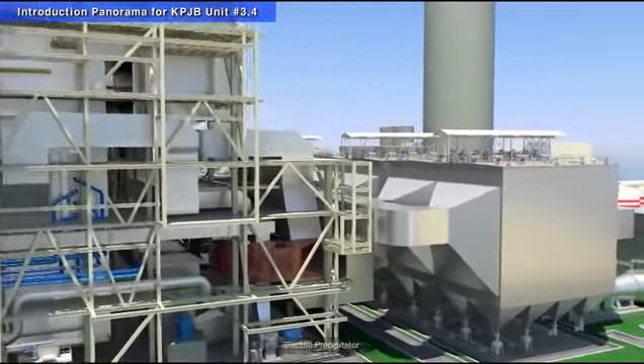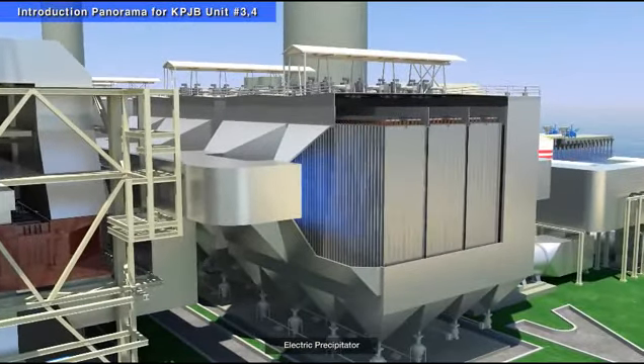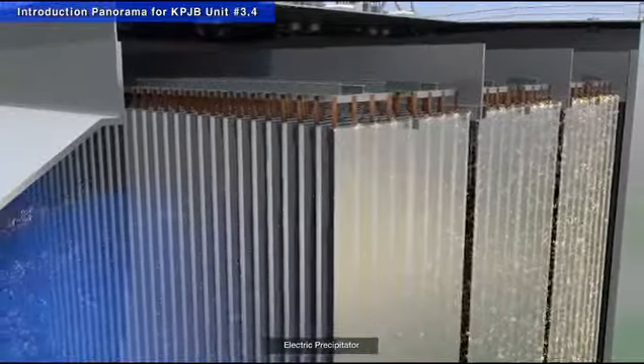In order to prevent the release of dust produced from burning coal, the exhaust gas of the boiler goes through the electrostatic precipitator to remove the dust by using the static suction force after making the dust in the exhaust gas electrified. This is done by using the corona discharge.